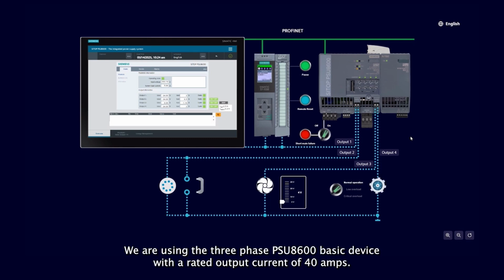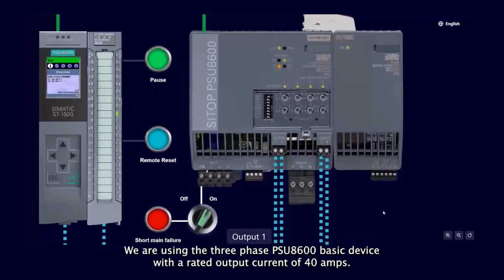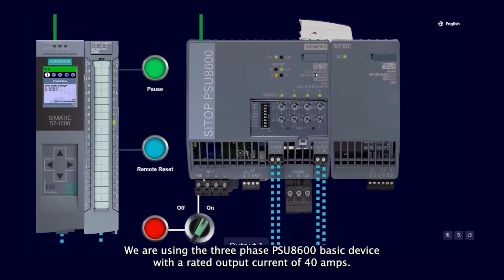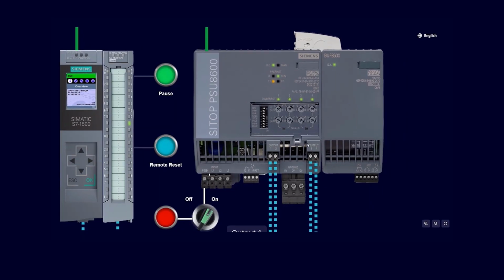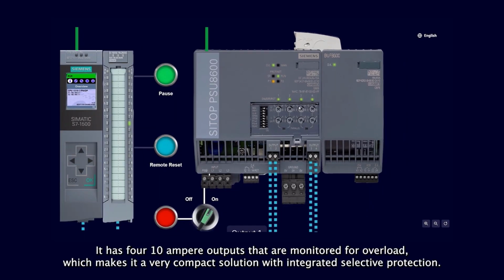We are using the 3-phase PSU8600 basic device with a rated output current of 40 amps. It has 4 10-ampere outputs that are monitored for overload, which makes it a very compact solution with integrated selective protection.